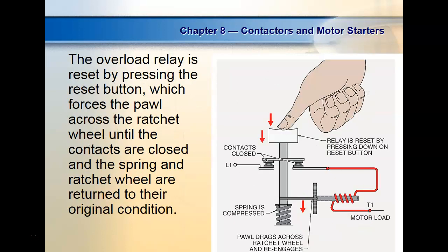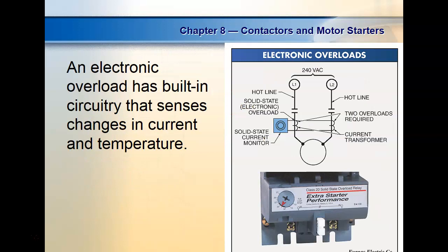So these guys have a reset on them. It used to be they had multiple ones, but now they have one that resets all three of them. Normally you'll see, when they draw your overloads, they'll sometimes put three of them out there. But now the tendency is to put just one, because you reset them with the same reset, even though it breaks all three in any line. Are we okay? Yes, no? We have these magnetic ones, they use current transformers. So it kind of works like a clamp-on ammeter. These are your electronic ones. And what's the problem with these?